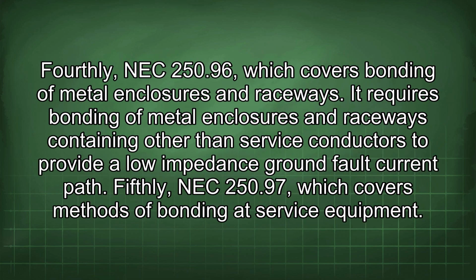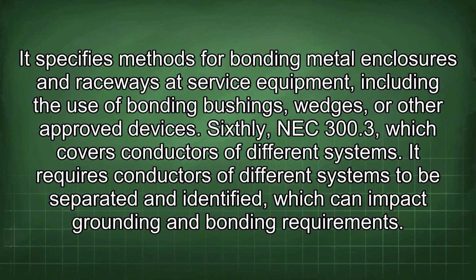Fourthly, NEC 250.96, which covers bonding of metal enclosures and raceways. It requires bonding of metal enclosures and raceways containing other than service conductors to provide a low impedance ground fault current path. Fifthly, NEC 250.97, which covers methods of bonding at service equipment. It specifies methods for bonding metal enclosures and raceways at service equipment, including the use of bonding bushings, wedges, or other approved devices.